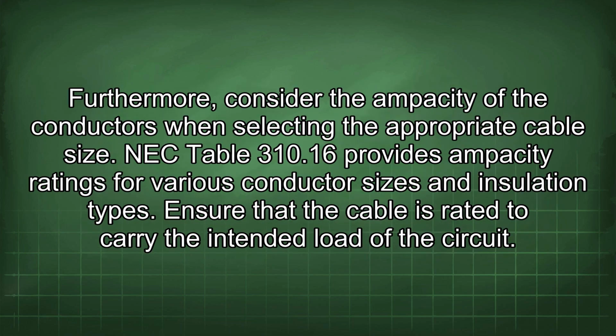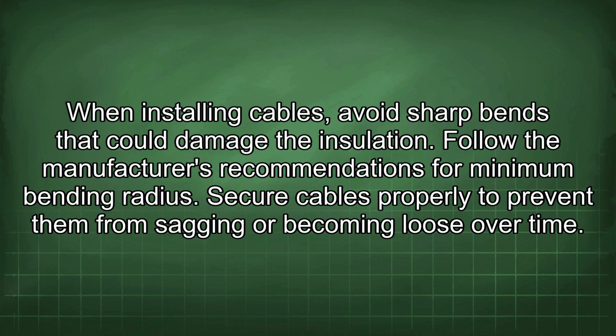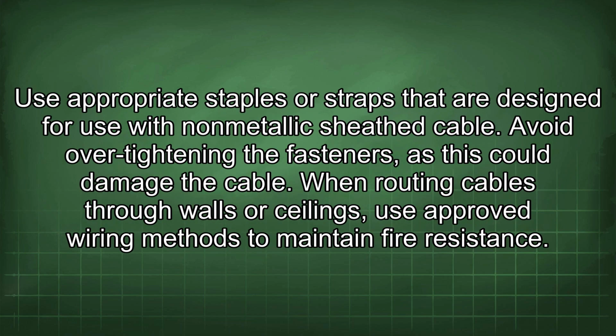Furthermore, consider the ampacity of the conductors when selecting the appropriate cable size. NEC Table 310.16 provides ampacity ratings for various conductor sizes and insulation types. Ensure that the cable is rated to carry the intended load of the circuit. When installing cables, avoid sharp bends that could damage the insulation. Follow the manufacturer's recommendations for minimum bending radius. Secure cables properly to prevent them from sagging or becoming loose over time. Use appropriate staples or straps that are designed for use with non-metallic sheath cable. Avoid over-tightening the fasteners, as this could damage the cable.